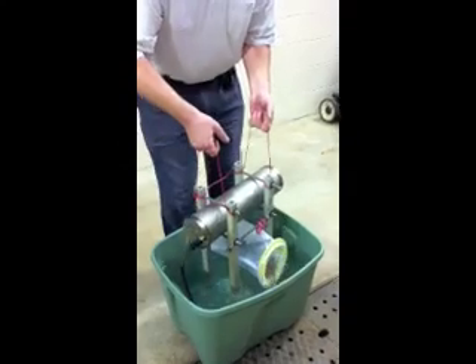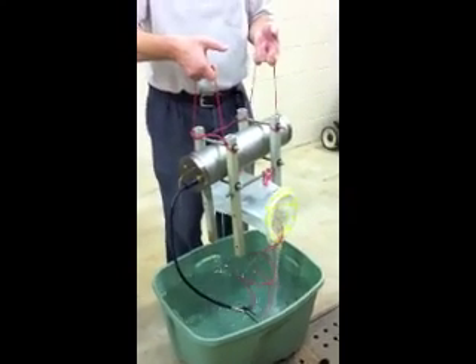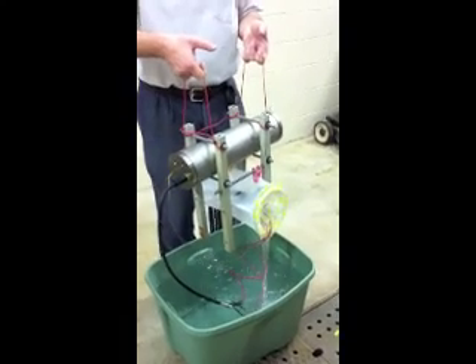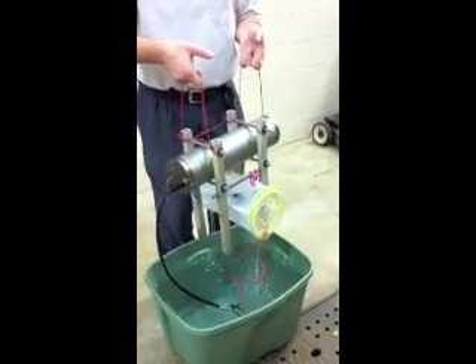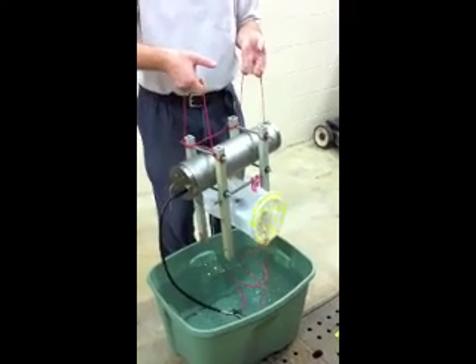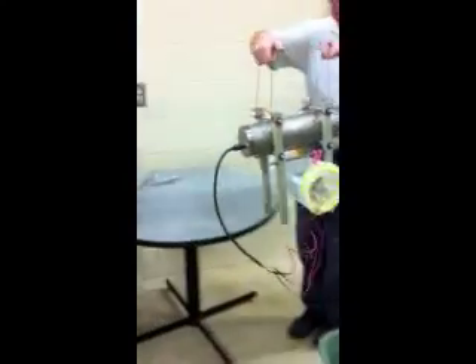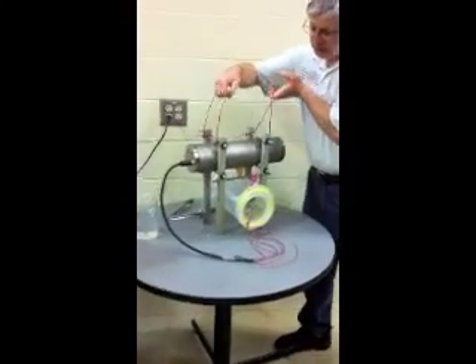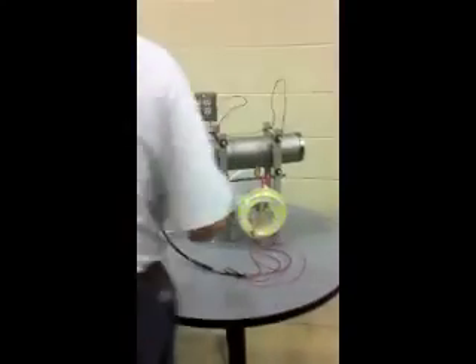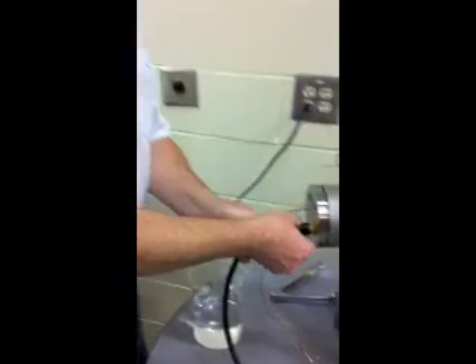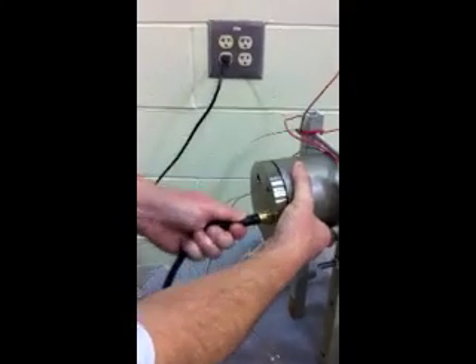Okay, once the test is over, we can recover our sensor from the test fluid. We can simply lift it out. Let it drain a second. Okay. On the table. First thing I'll do is remove the cable, loosen the sleeve, and again pull straight out, jiggle just a little, don't twist, and there, that is done.